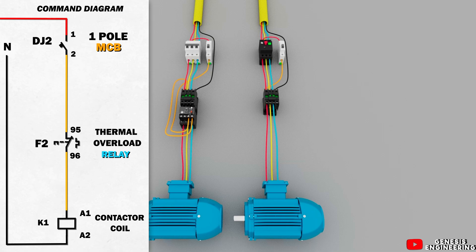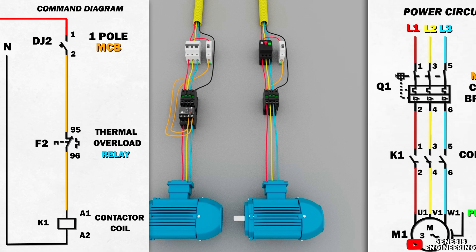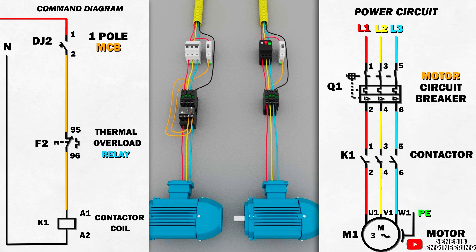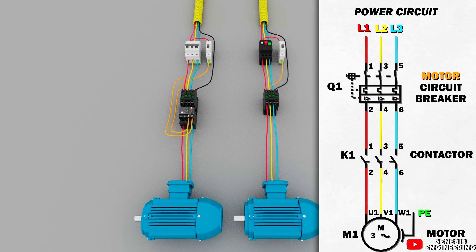When we use the thermal relay to protect the motor, we have indirect protection — the thermal relay does not open the power contacts on overload, so it is necessary to use a contactor. We place the normally closed contact 95 and 96 of the thermal relay in series with the contactor coil, and the contactor opens the power contacts to switch off the motor. With the motor circuit breaker the protection is direct, because the motor circuit breaker's power contacts will open directly to turn off the motor in case of overload.